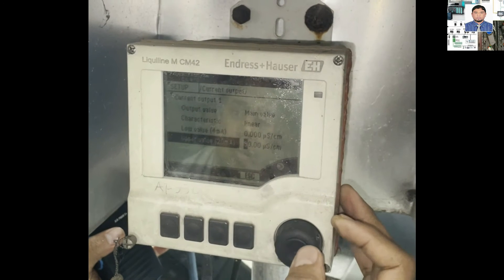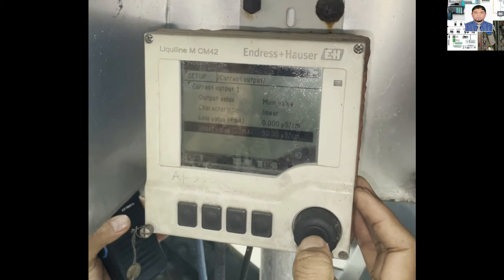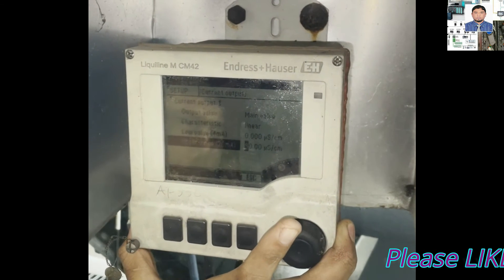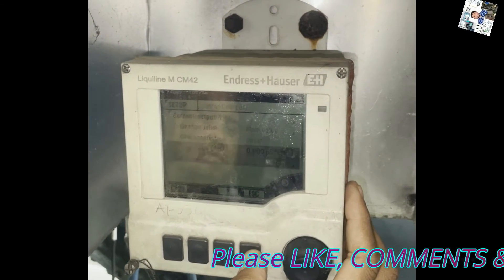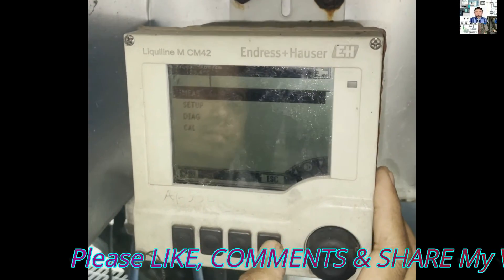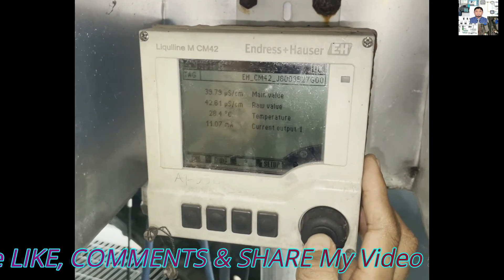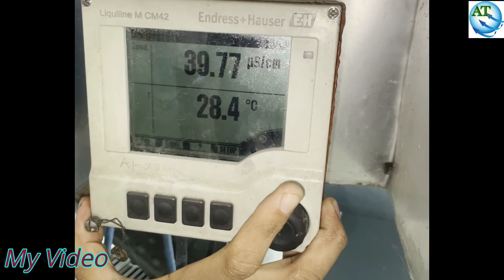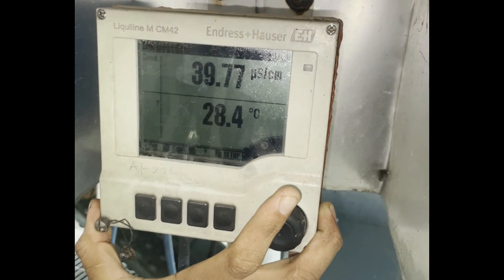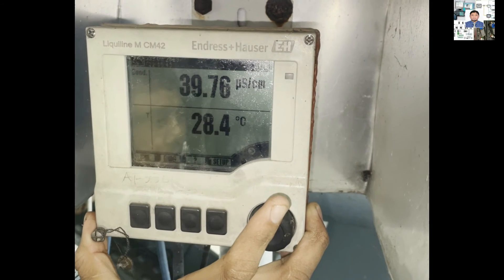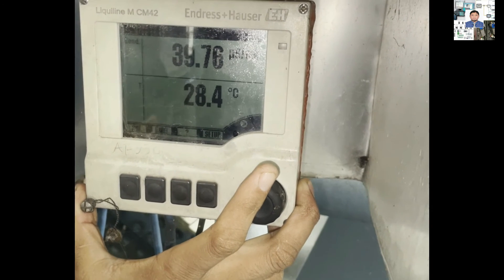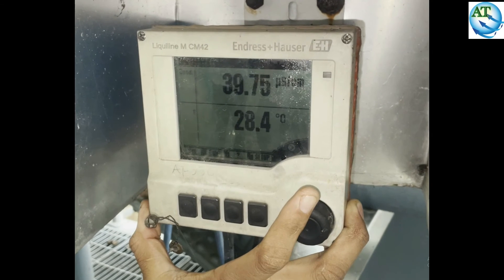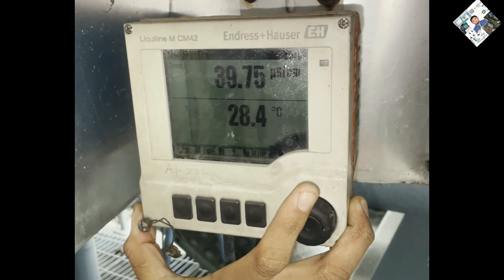If you set these three elements correctly, then you can get the accurate value from this transmitter. First, select which transmitter you are using — conductivity, pH, oxygen, or DO transmitter. That means the Liquiline M CM42 model — this Endress+Hauser transmitter can be used for pH meter, conductivity, or oxygen analyzer. So first you have to select that, then configure and calibrate the transmitter as per the standard solution or standard sample. If this is done correctly, the transmitter will work properly and show accurate values.